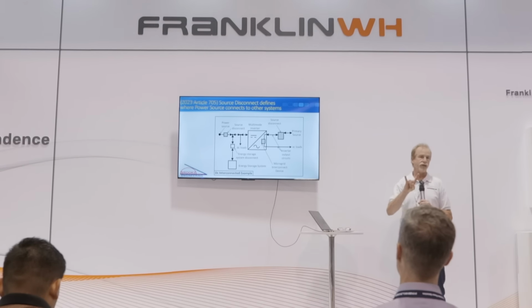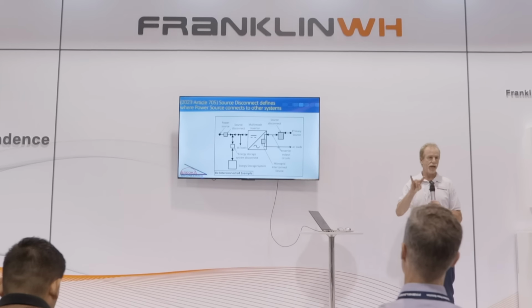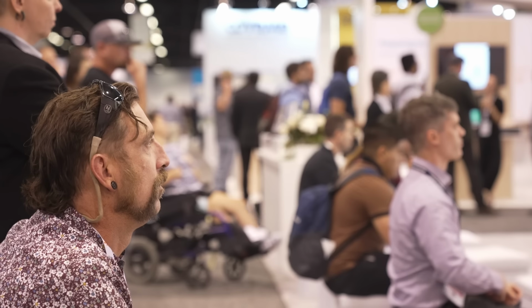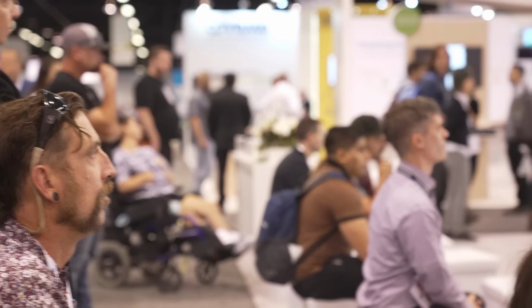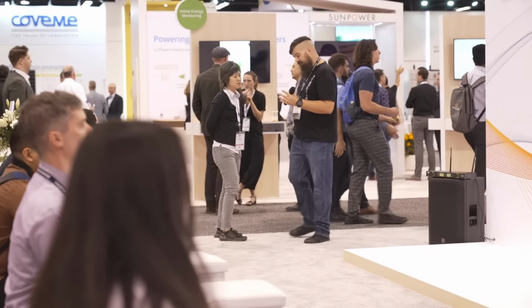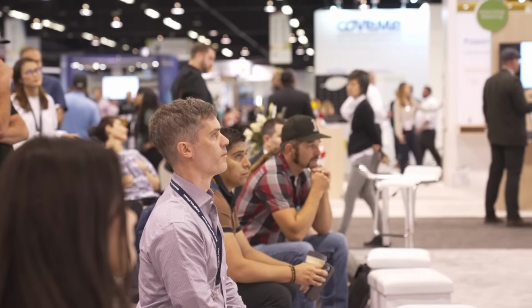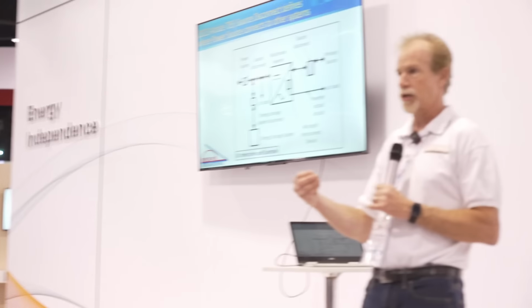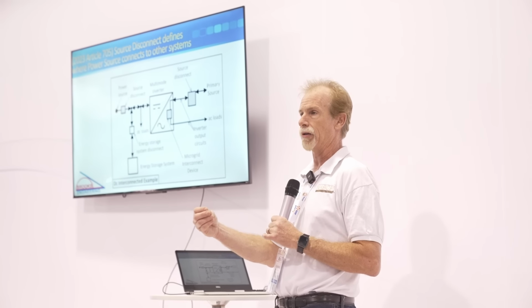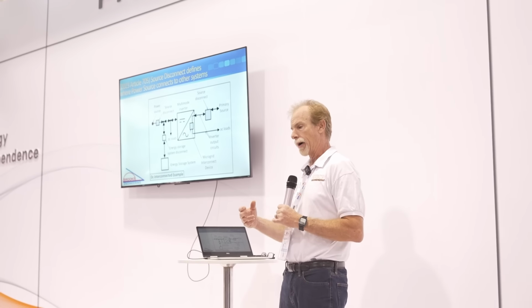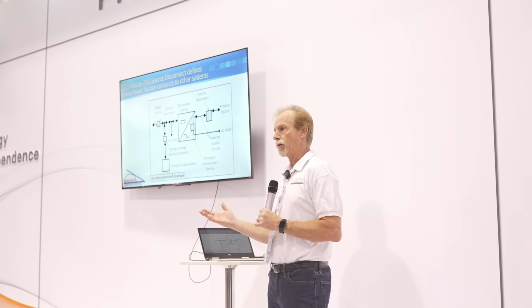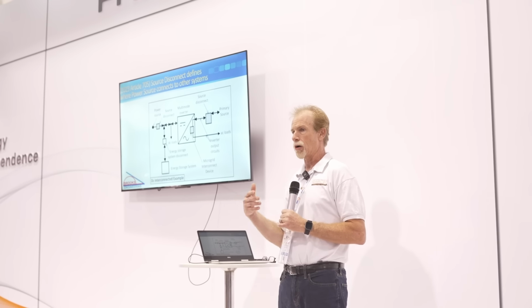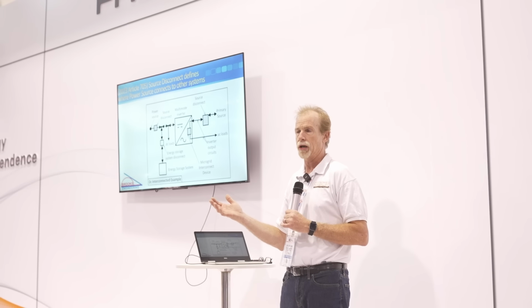And there's two things that are essentially off the list when we're talking about AC coupling and batteries. The first one is line side taps, or what people call line side taps. The correct term would be a supply side connection to a service, okay? So we could have a source connection to a service, which is what it's termed now in the 2023 code. But that does us no good with the battery storage system unless all we're going to do is energy arbitrage.